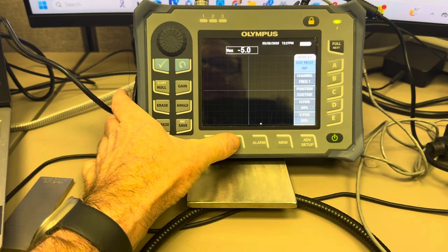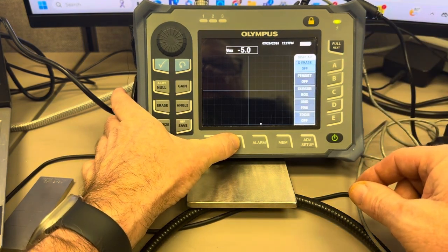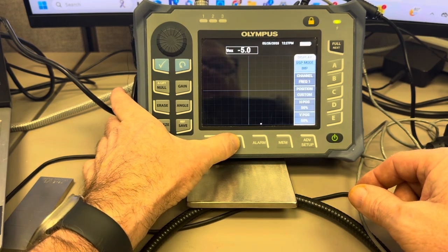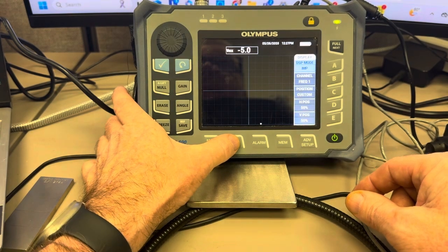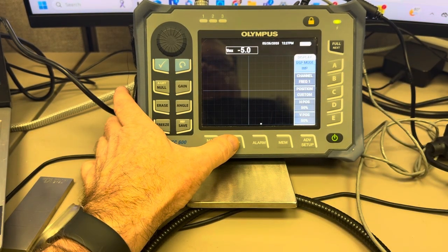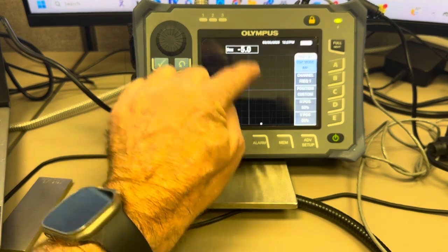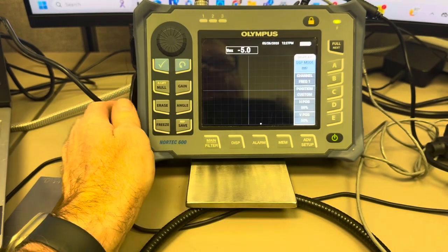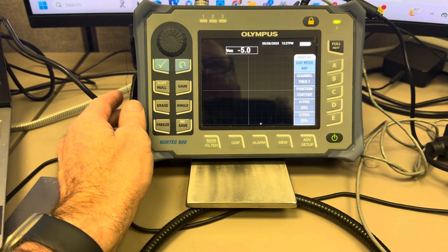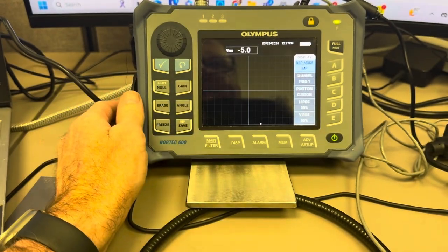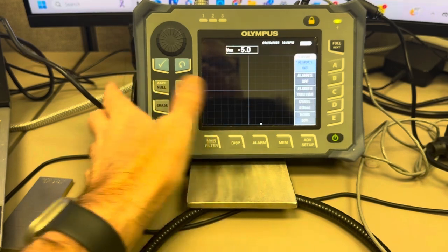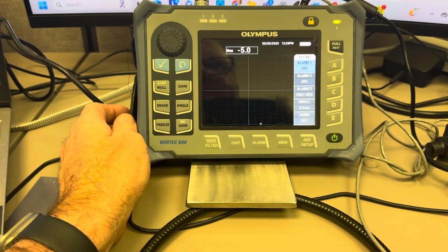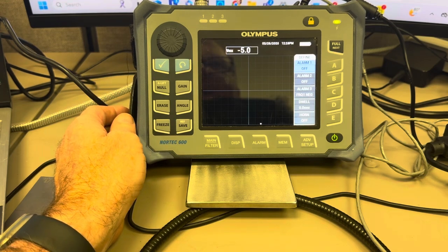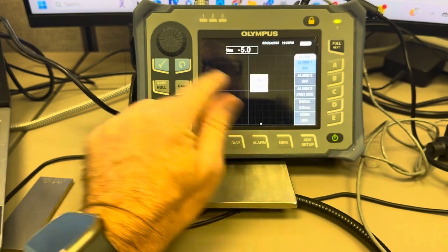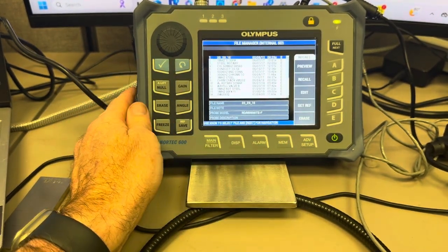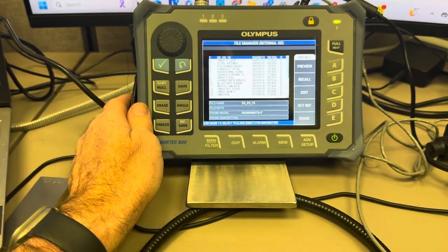All right, then if you go into the display mode, it changes it obviously over here. Now you can go through this display mode. Looks like there's 3 or 4 different menus in there. But the display menu provides access to controls which position the vector point, your impedance point. You can move that around the screen to anywhere you want it to be. The trace, the style of grid, whether you're using a polar grid or Cartesian grid, you can adjust that to your preference. The alarm menu provides access to control functions such as type of alarm, dwell time, how loud the beep is, and the position of your alarm gates. And you have your memory key there that gets you into the storage screen. This shows all the setups that have been previously stored in the instrument.